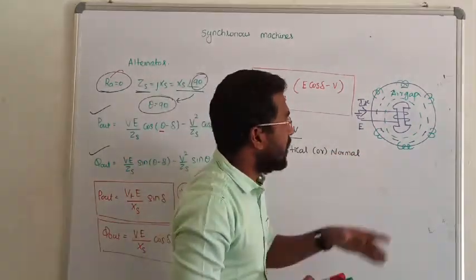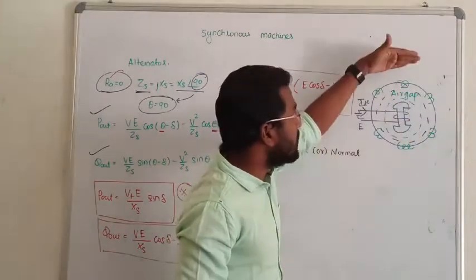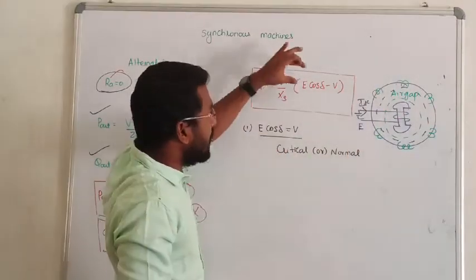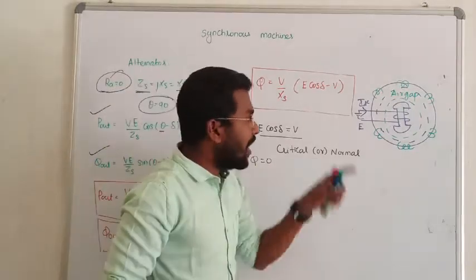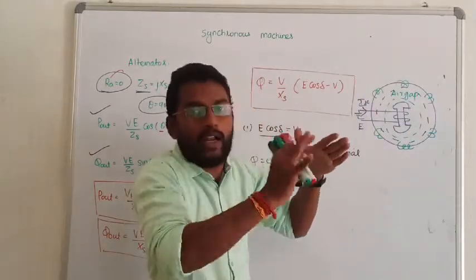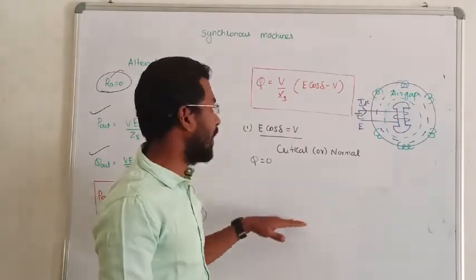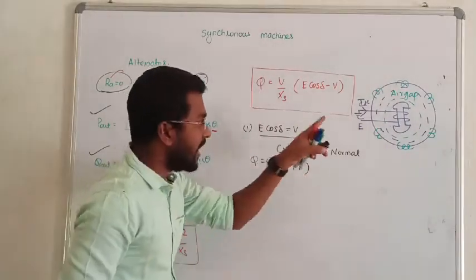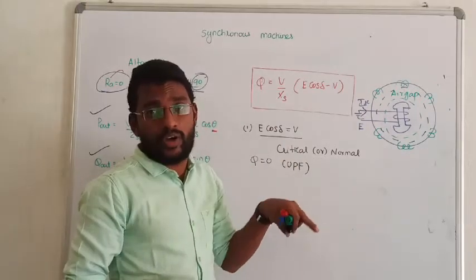Under normal excitation, the reactive power supplied by the alternator is going to be zero. The alternator operates at unity power factor. It is neither supplying leading reactive power nor absorbing reactive power.